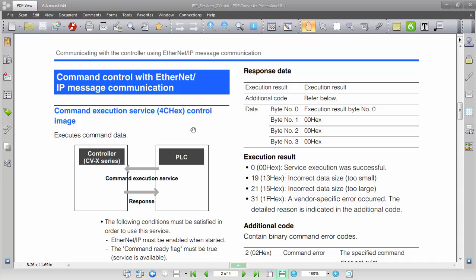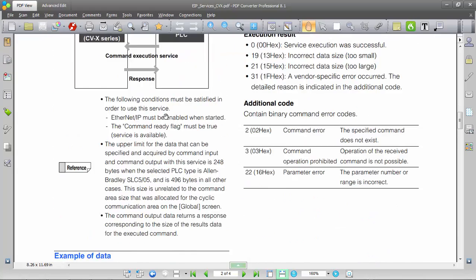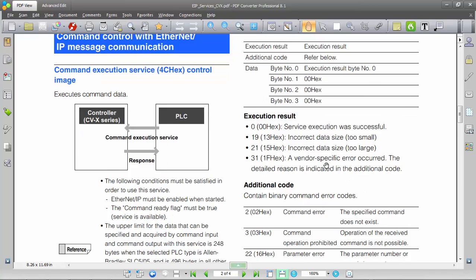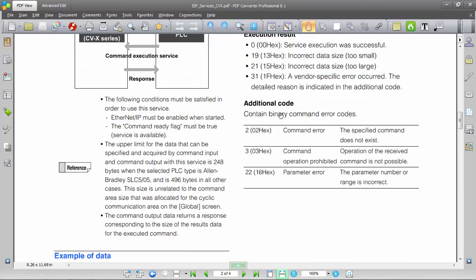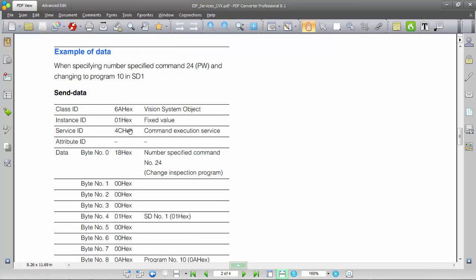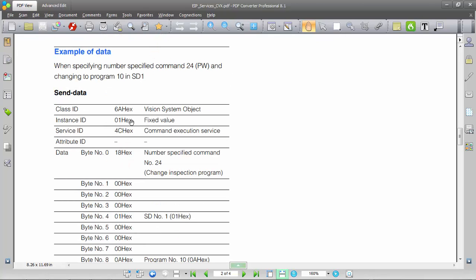Here's the section from the manual for the EtherNet/IP message service for control command execution. Hex code 4C is going to be the command execution service. We're going to receive four bytes — the receive information will contain any additional code information like command error or command operation prohibited. The send information will vary depending on the command you're executing, so you'll need to refer to the user manual to find out which command parameters are needed.